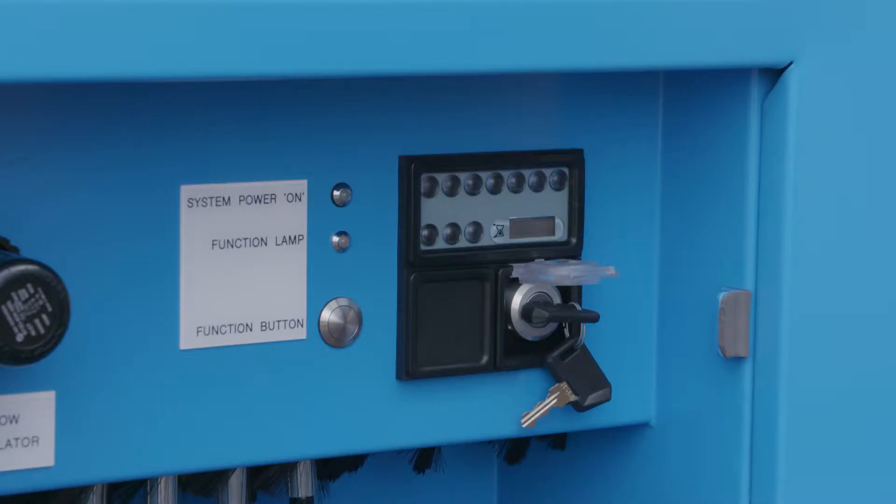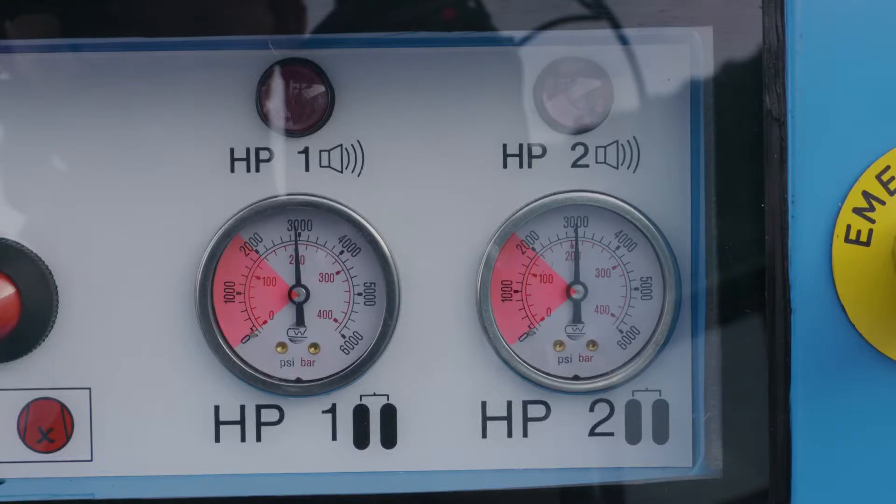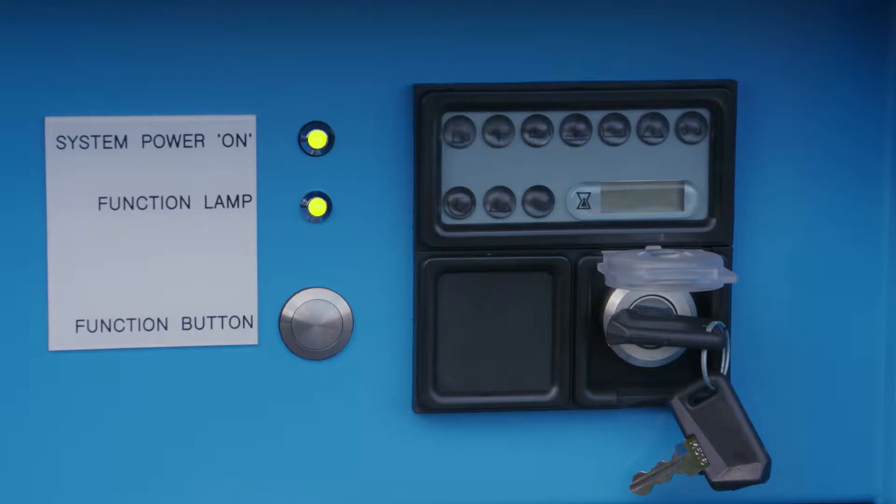To begin the retest, press the function button. If cylinder pressures are below 135 bar, they must be refilled or replaced before subsequent use. Once the engine has stopped, two indicator LEDs next to the function button will continue to be lit for five minutes. This is normal.